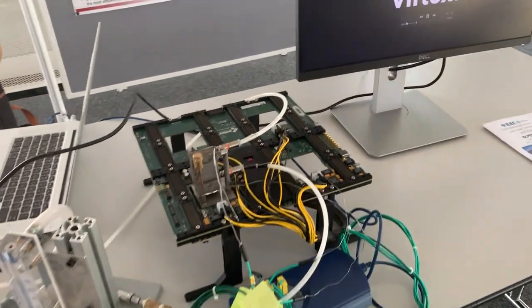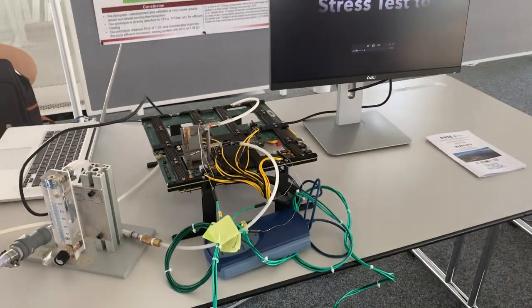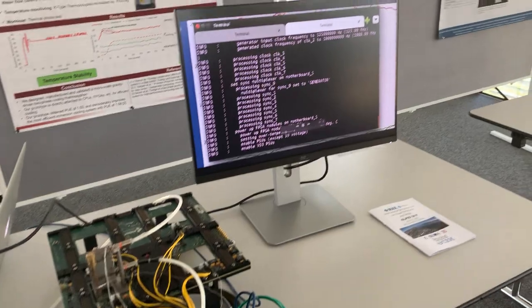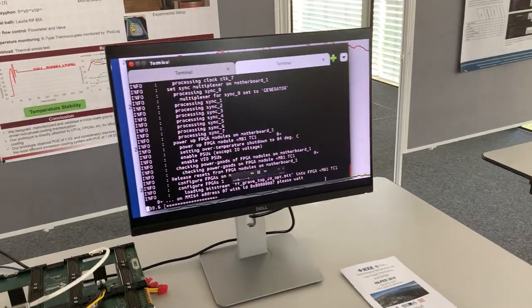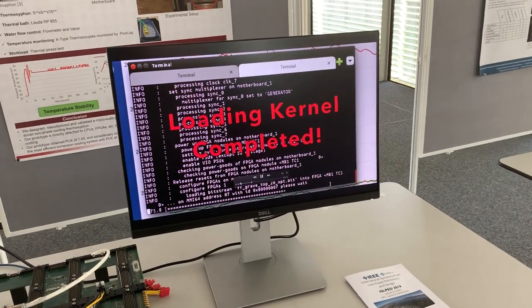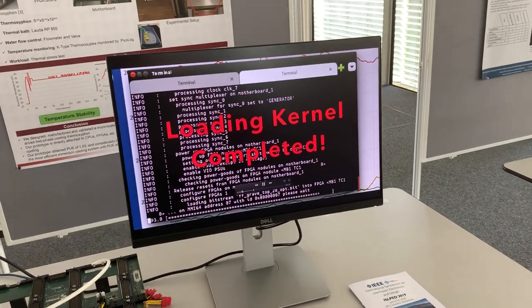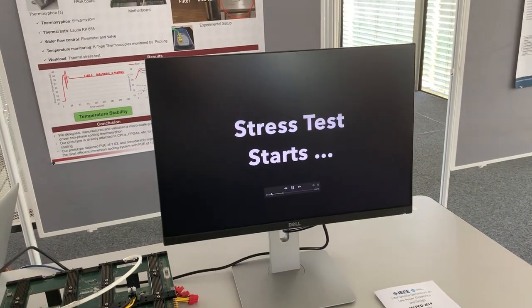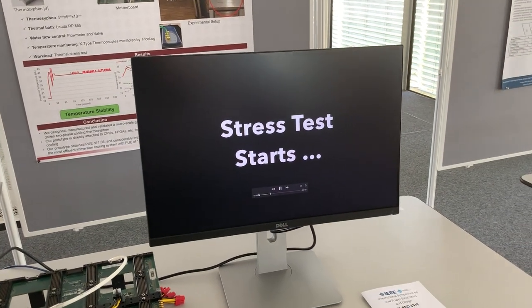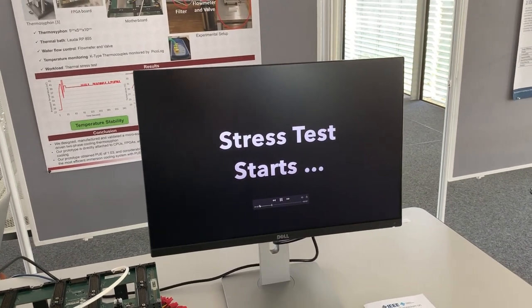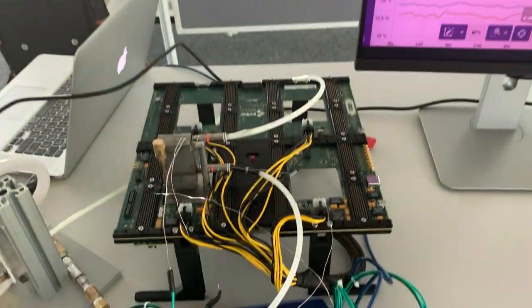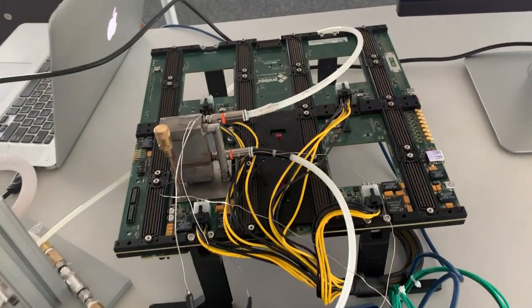So what we do here is that we use a thermal stress test on top of Virtex-7. So we first load the thermal stress test and when it starts, we see that the temperature at different parts of the thermosyphon starts to go up.